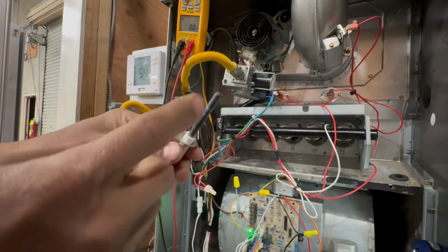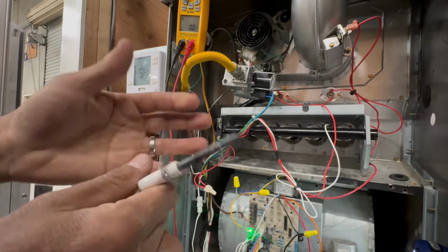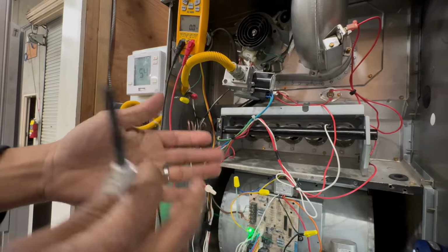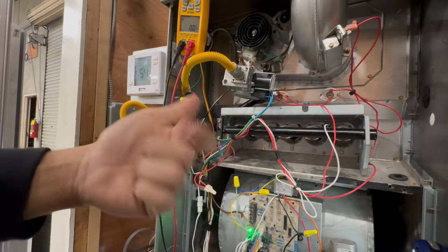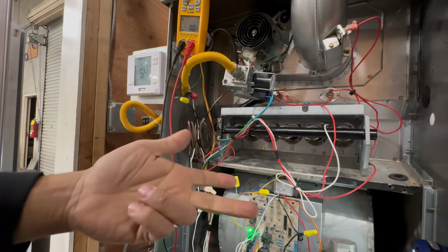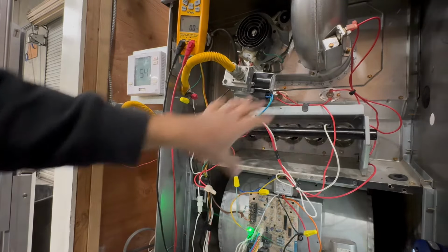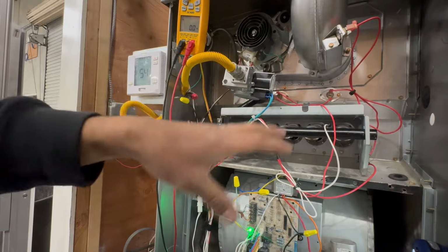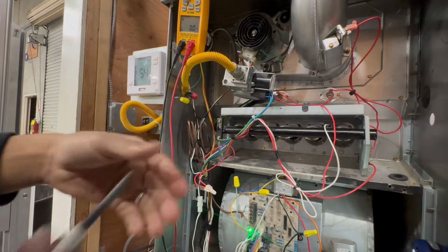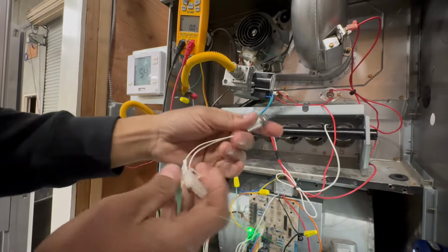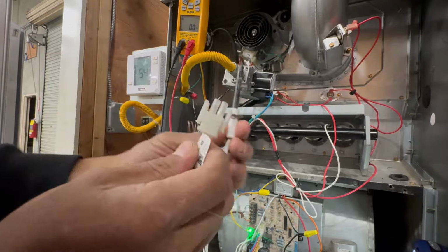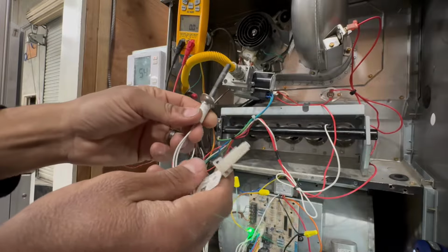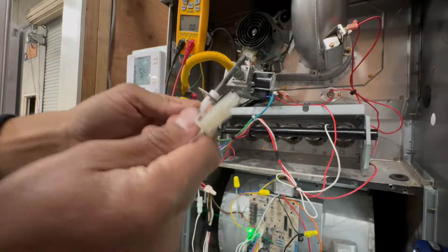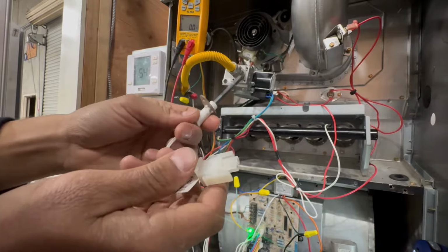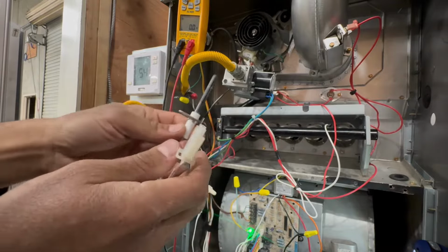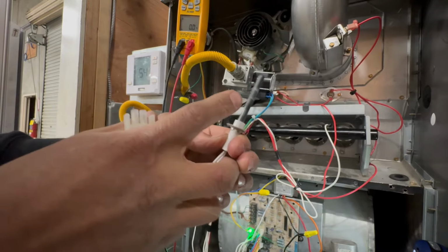So this is the part that turns cherry red, right? Because to produce fire, you need fuel, oxygen, and a spark. So in this case, we have some oxygen, right? It's pulling a draft. We got oxygen. We have the gas, which is my fuel, and we have the spark. So a hot surface igniter, this one's simple. This one receives 120 volts. So you know that it's receiving 120 volts, obviously, because it's turning cherry red.